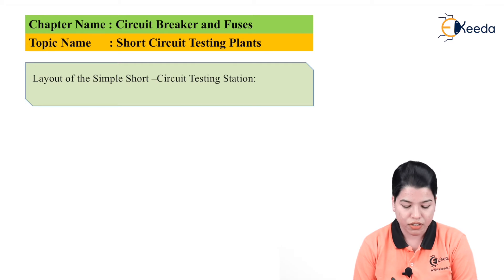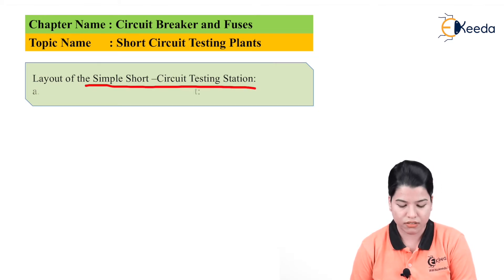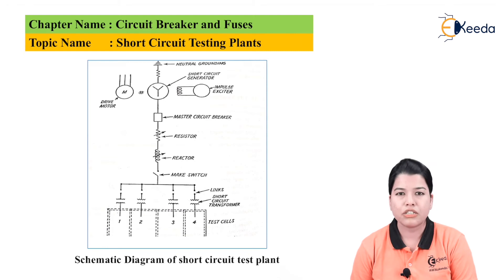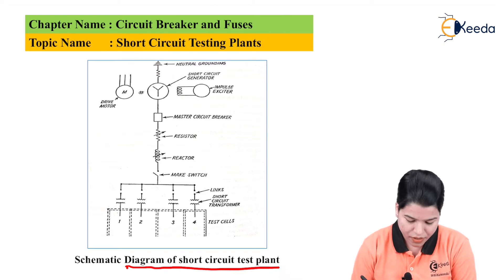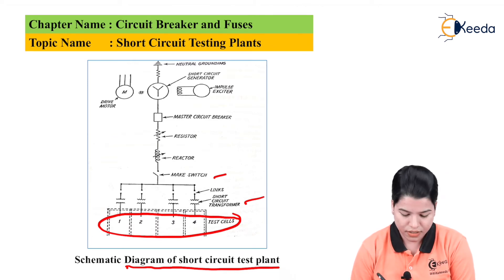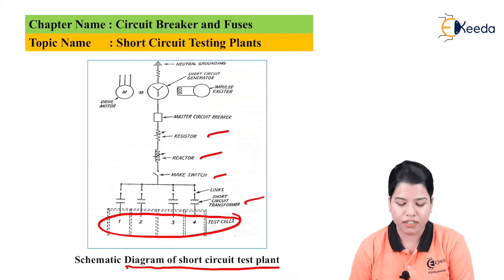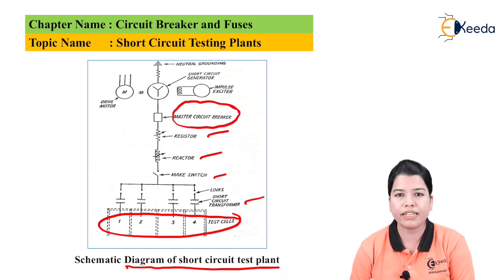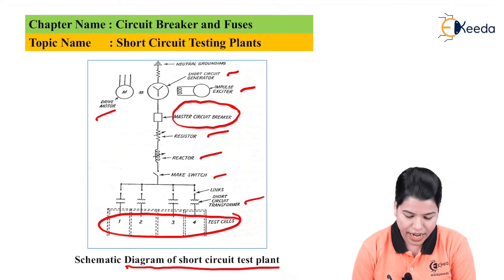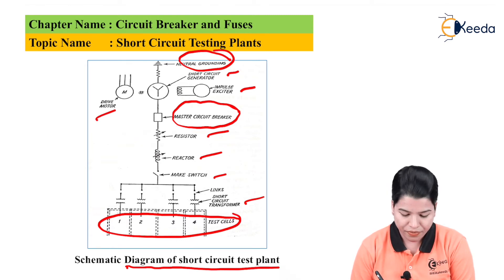Now let us see the layout of a simple short circuit testing station. The schematic diagram shows various test cells, short circuit transformers, a make switch, a reactor, a resistor, and the master circuit breaker. One impulse exciter is needed, along with a drive motor coupled to the short circuit generator, and neutral grounding. The master circuit breaker is connected so that if the circuit breaker under test fails to operate, the master circuit breaker will protect the complete system.